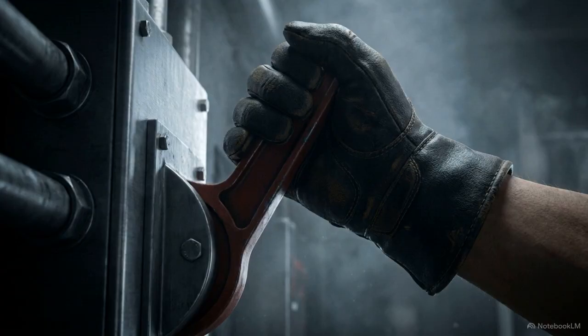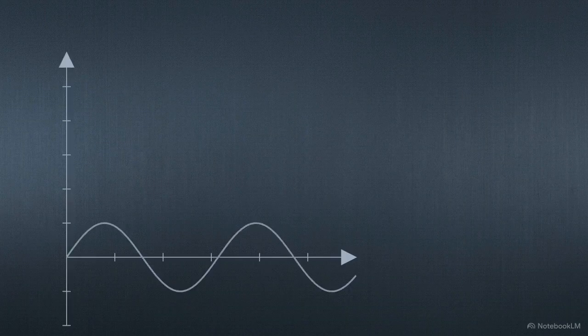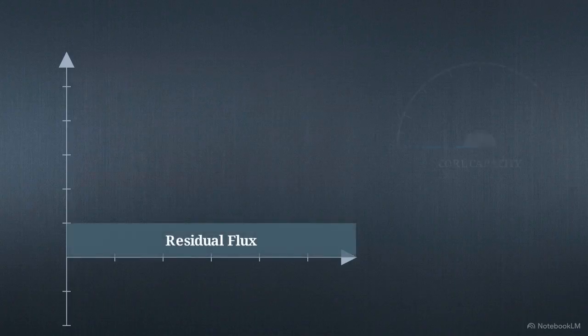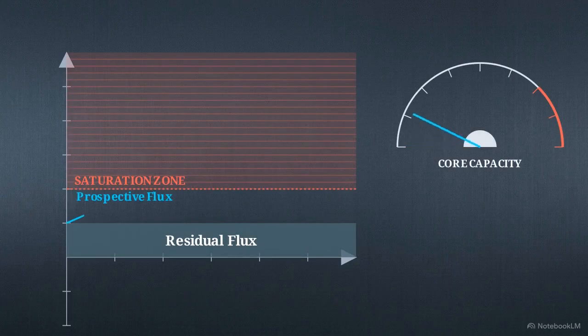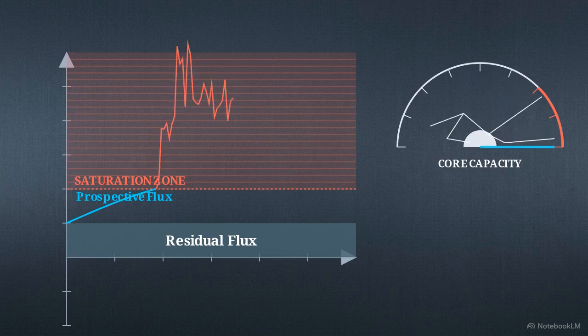The danger arrives when a grid operator blindly flips the switch to turn the machine on, striking the transformer at a random point on the alternating current wave. If the incoming wave stacks perfectly on the trapped residual flux, it pushes the core's capacity past its limit. At saturation, it acts as a short circuit, drawing an inrush current, a surge 8 to 15 times normal capacity.